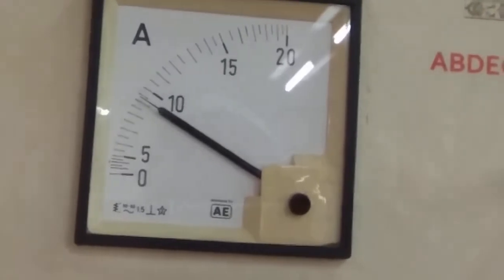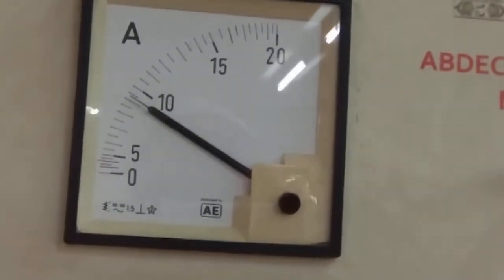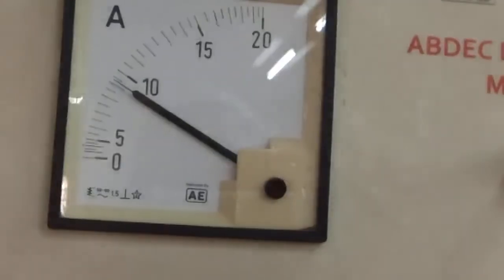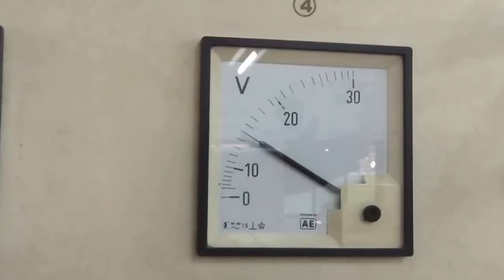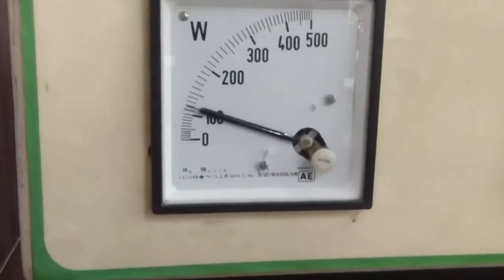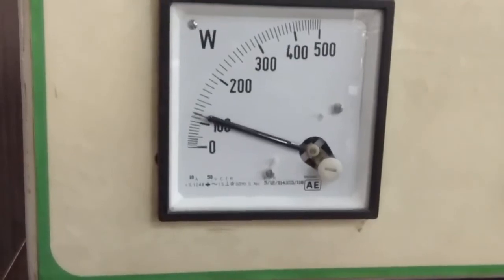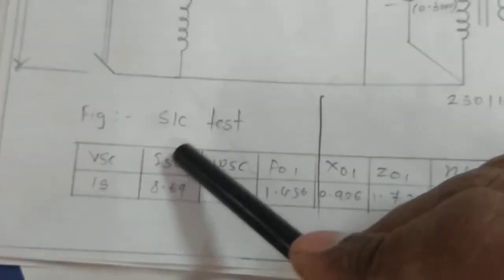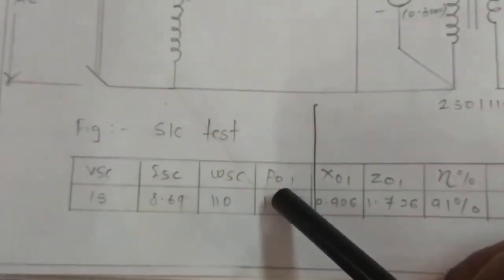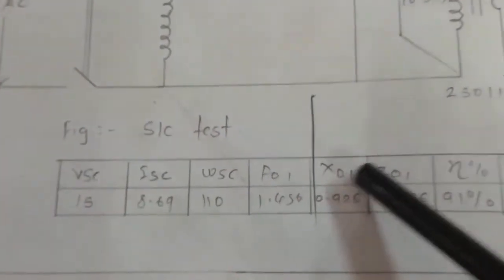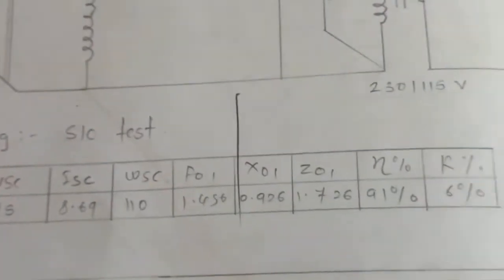Then we will note down all the readings in the observation table. At that same time, the voltage is 15 volt, you can see here, and the wattmeter is showing 110. We will note down all the readings, voltage, current and power, in the observation table. After that, we will do the calculation for R01, X01, Z01, efficiency and regulation, and we will note down all the calculated readings also in this observation table.